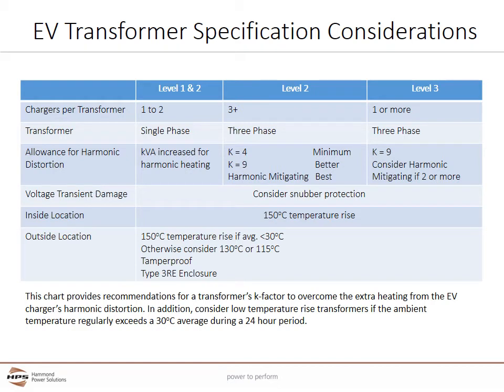In reality, the lack of a balanced load across the three phases with Level 1 and 2 chargers can cause additional problems, and a K factor of 9 is preferred. A K factor of 9 is also preferred with Level 3 chargers. The best solution, especially for meeting IEEE 519 for large numbers of Level 1 and 2 chargers or 2 or more Level 3 chargers, is using harmonic mitigating transformers to actually cancel the harmonic currents. Another issue is ambient temperature, especially in outdoor installations in southern North America. If the average 24-hour temperature commonly exceeds 30 degrees Celsius, lower temperature rise transformers at 130 or 115 degrees Celsius should be specified.